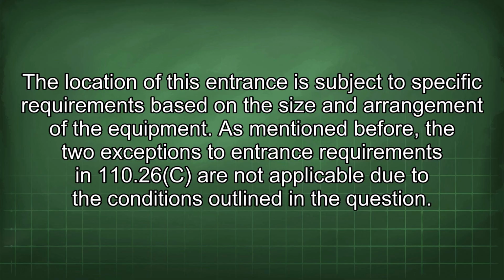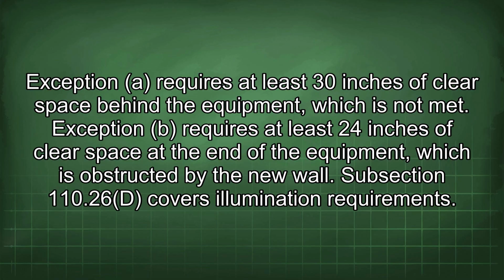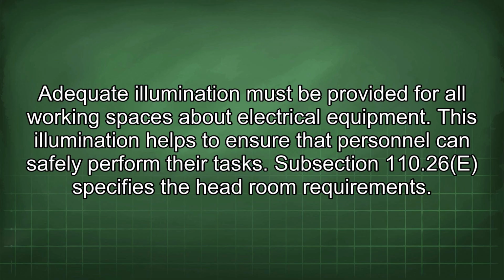As mentioned before, the two exceptions to entrance requirements in 110.26c are not applicable due to the conditions outlined in the question. Exception A requires at least 30 inches of clear space behind the equipment, which is not met. Exception B requires at least 24 inches of clear space at the end of the equipment, which is obstructed by the new wall. Subsection 110.26d covers illumination requirements. Adequate illumination must be provided for all working spaces about electrical equipment. This illumination helps to ensure that personnel can safely perform their tasks.